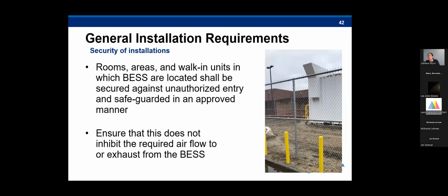So here we are, still in the general installation requirements, and this is the security of installations requirement. You want to ensure that the systems are secured against unauthorized entry and safeguarded in an approved manner. Security barriers, fences, landscaping, and other enclosures should not be used to inhibit any required airflow or exhaust from the system. Also, the energy storage system has a lot of stored energy that could injure people when they come in contact with the system. So you just want to make sure that these systems, especially if they're outside, have a fence around them, and if they are in rooms or indoors, that they're secured from any unauthorized entry.